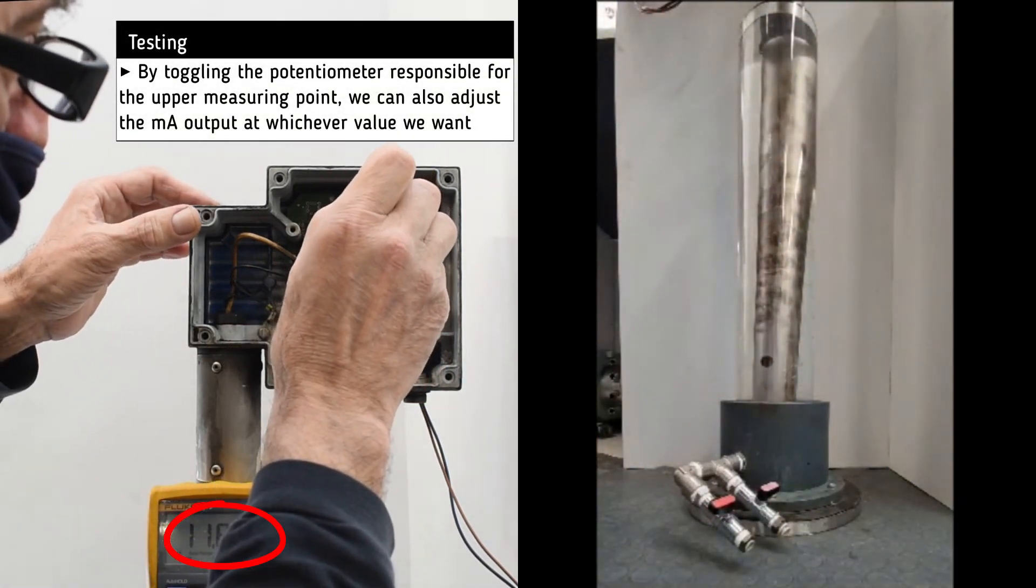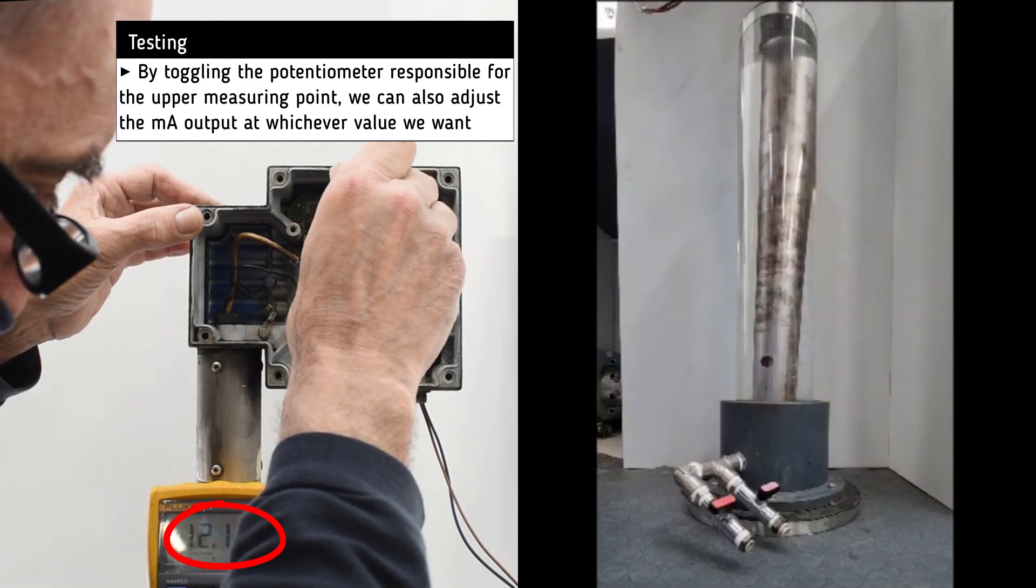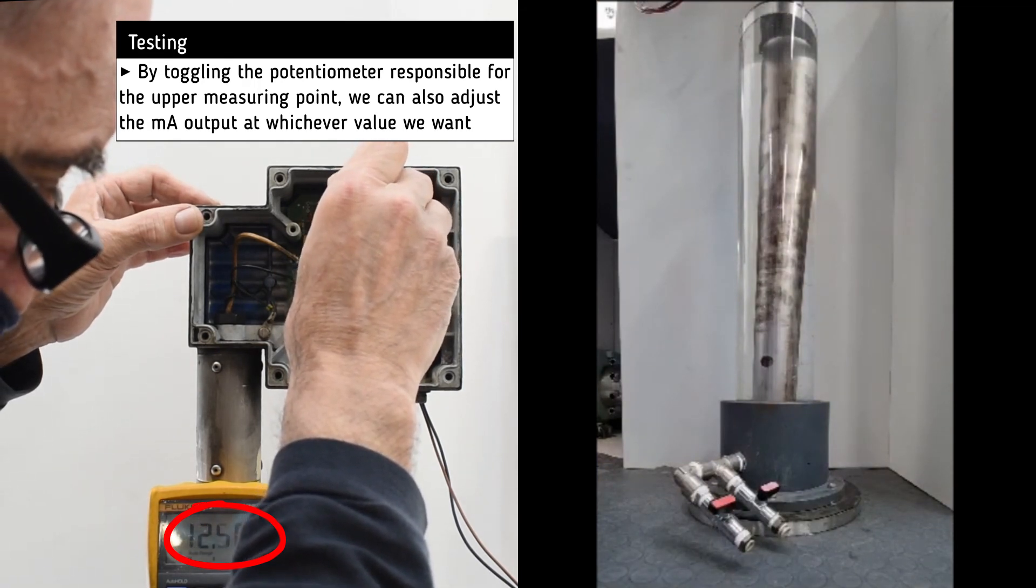By toggling the potentiometer responsible for the upper measuring point, we can also adjust the milliamp output at whichever value we want.